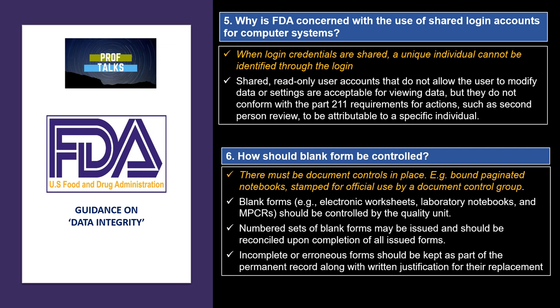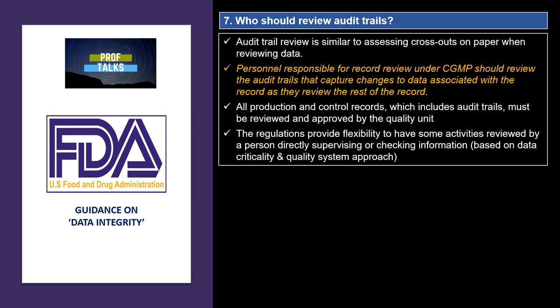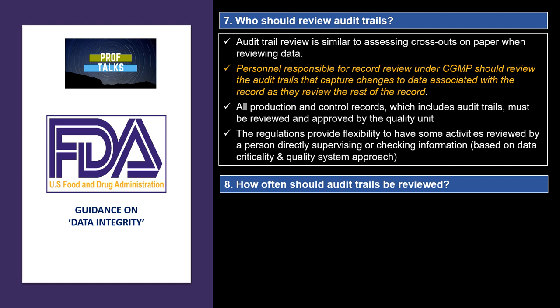Who should review the audit trail? The review of the audit trail is an activity similar to the review of a paper record. Whoever is responsible for the review of a CGMP record should review both the electronic record and the audit trail. All production and control records, which include the audit trail, must be reviewed and approved by the quality unit. Regulations provide flexibility to have some activities reviewed by a person directly supervising the activity.